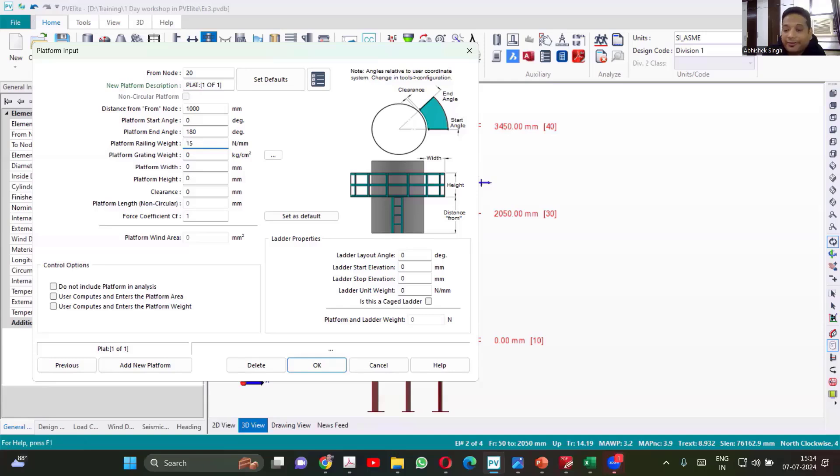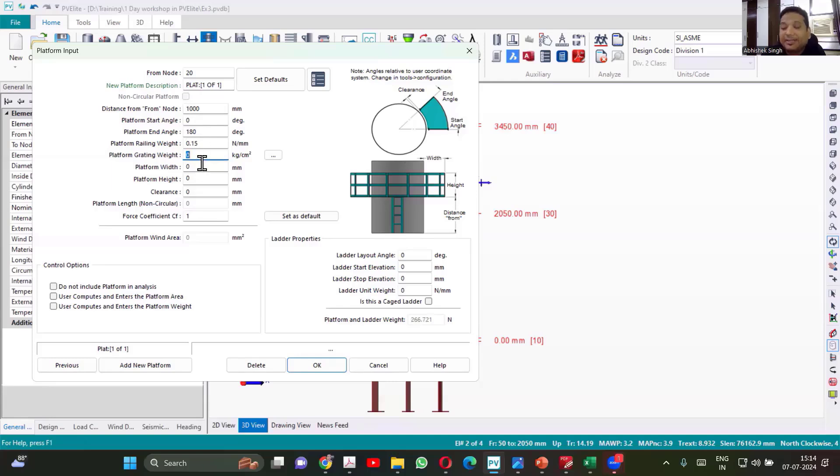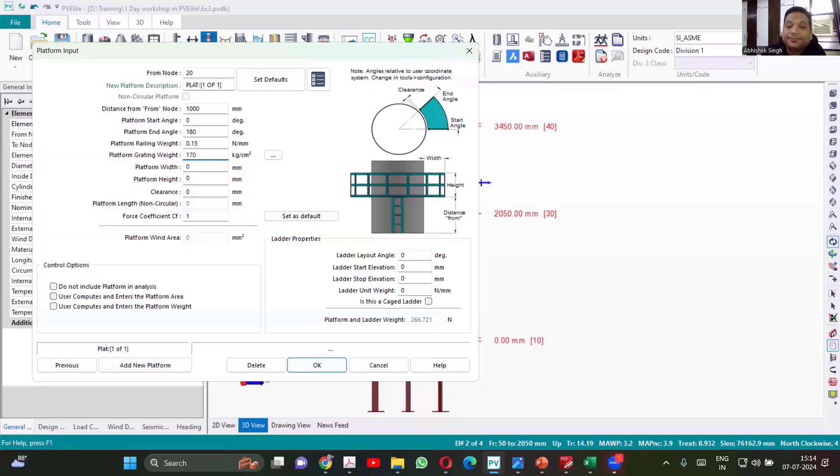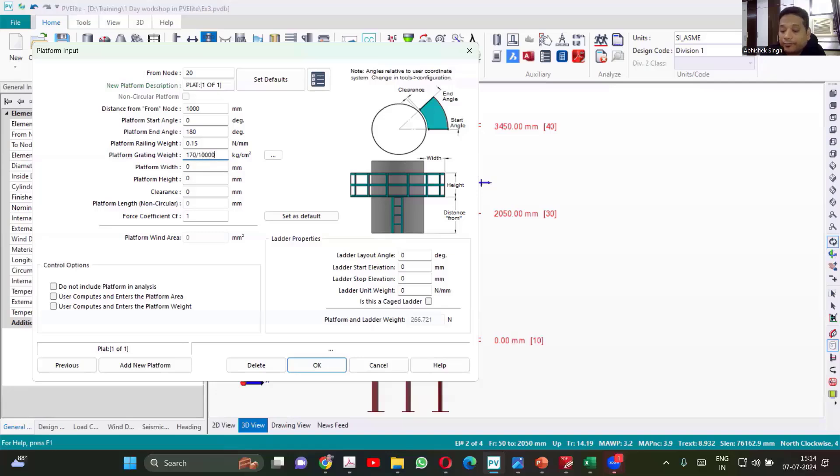Platform railing weight. Railing weight of the platform typically you can consider as 10 or 15 kg per meter. So 15 kg means it will be 150 newton divided by 1000. So this is the standard platform railing weight. Platform grating weight we consider 160 kg per meter square or 170. So if we take 170 kg per meter square, 170 into 10,000 is what we will divide. So that is your platform grating weight.